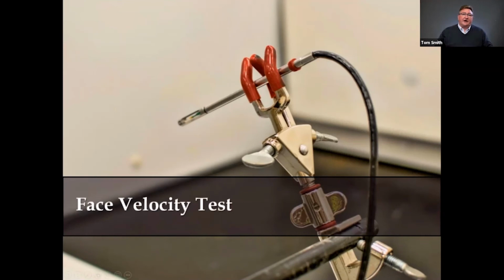And so we use a hot wire anemometer. The hot wire probe has heated elements, and that allows measurement of very low velocities, about 30 feet per minute, and sometimes less. As the air moves over the probe, it cools, and that results in a change in voltage, which allows us to indicate the average face velocity, or the velocity at that period of time. And we want to mount that on a stand, so as to be held stationary at that point in the sash to prevent the error associated with a handheld probe.